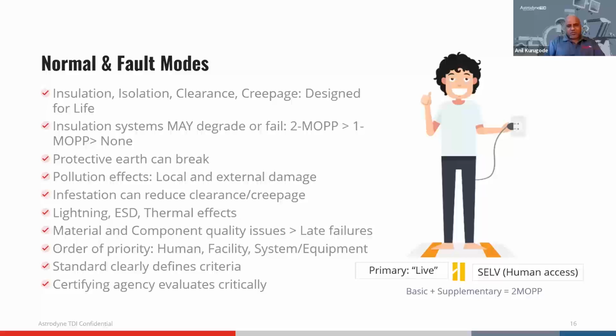For example, there's leakage current testing, where in normal mode everybody expects you to be below 100 microamperes for the body floating, or BF type. But when something really goes bad, which is very rare, the safety agencies recognize that for that abnormal situation, a higher level of leakage is allowed, because the belief is that if something goes wrong, some action will take place and it will be remedied, or at least there'll be a caution sign saying do not use, and it'll be taken out of service.